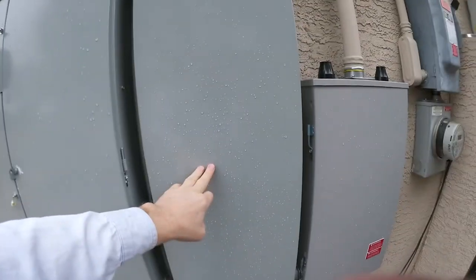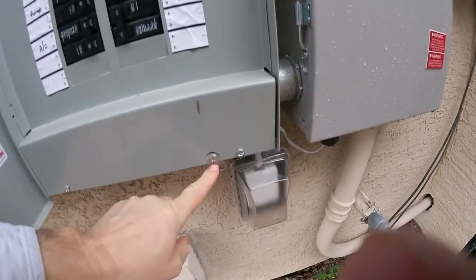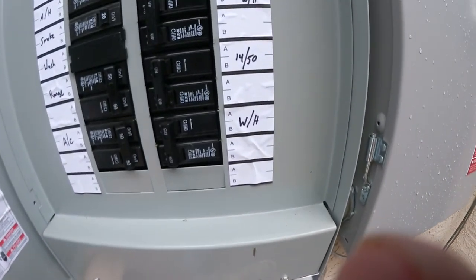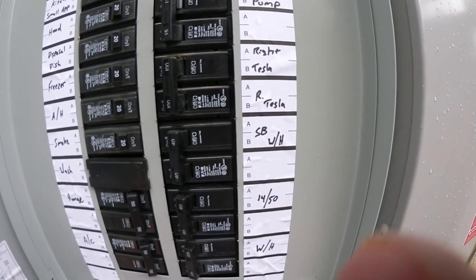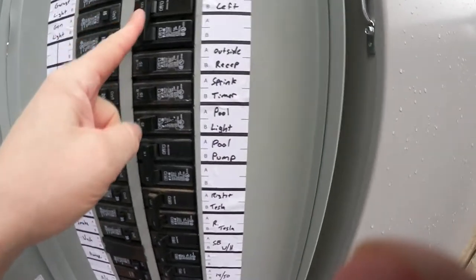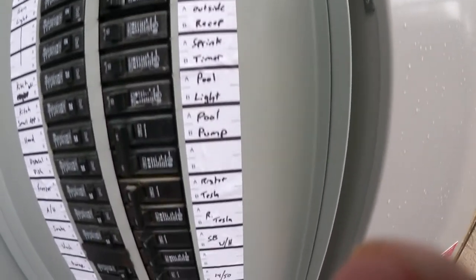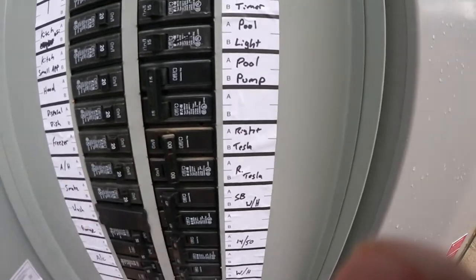So that is the breaker box after the Powerwall, and you open it from the hook here, and then you are looking for the Tesla charger. So that is a 100 amp fuse. And there are two, one from the left and one from the right. So, turning off the right first.